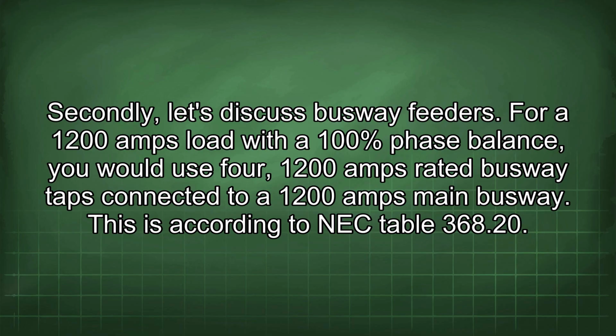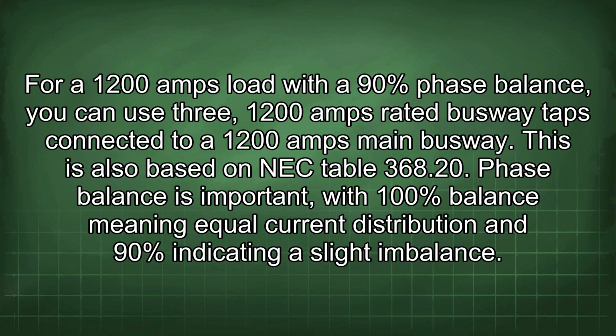Secondly, let's discuss busway feeders. For a 1200 amps load with a 100% phase balance, you would use 4 1200 amps rated busway taps connected to a 1200 amps main busway. This is according to NEC Table 368.20.